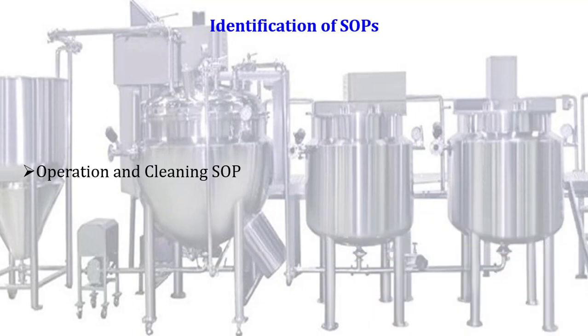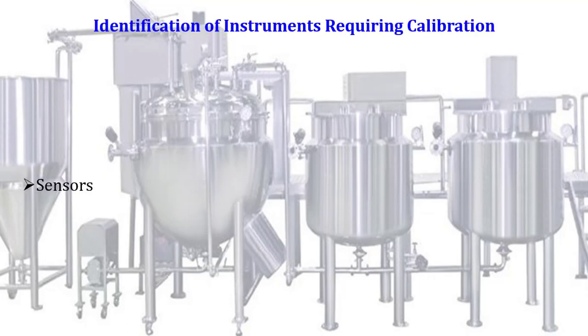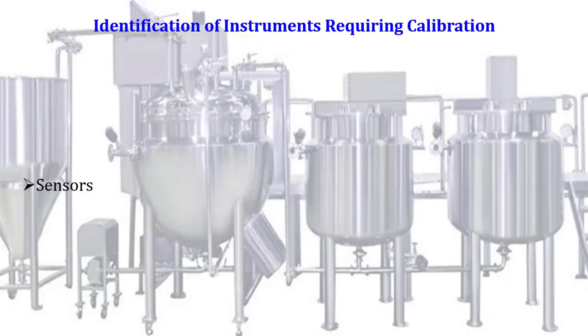Identification of SOPs is the next stage of installation qualification, in which we identify the SOP for operation and cleaning, and preventive maintenance SOPs. The next stage is identification of instruments requiring calibration. In case of an ultra-low deep freezer, only two components or instruments require calibration. In case of other equipment, there are a number of sensors or gadgets that need to be calibrated prior to operational qualification.